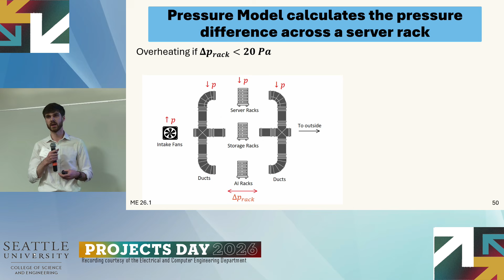And what it checks for is if that pressure difference is above or below 20 Pascal. If the difference is below 20 Pascal, the model will report that the system is overheating. And the reasoning behind this is if we have an insufficient pressure gradient, the hot air leaving the racks can actually flow back into the racks, causing the overheating.